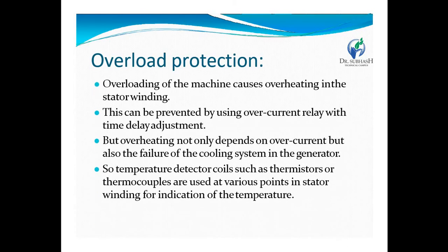Overload protection, where overloading of the machine causes overheating in the stator winding. This can be prevented by using an overcurrent relay with time delay adjustment. But overheating not only depends on overcurrent but also on failure of the cooling system in the generator. So temperature detector coils such as thermistors or thermocouples are used at various points in the stator winding for indication of the temperature.